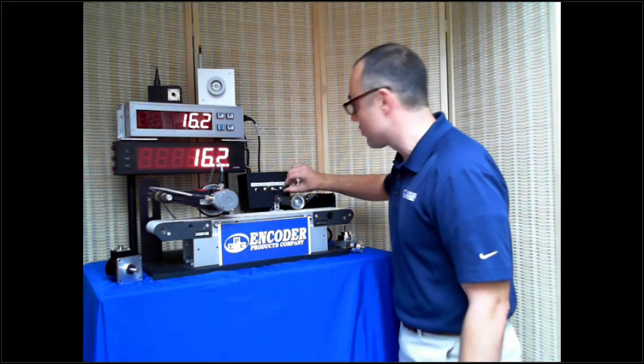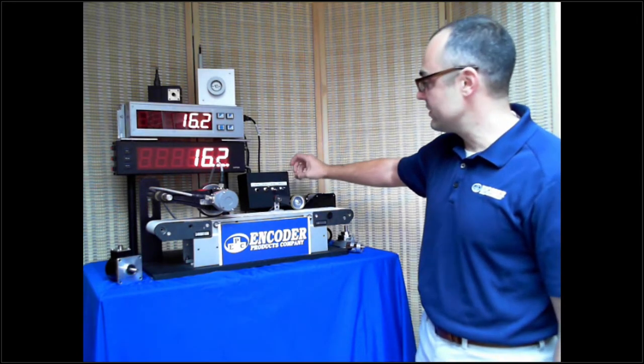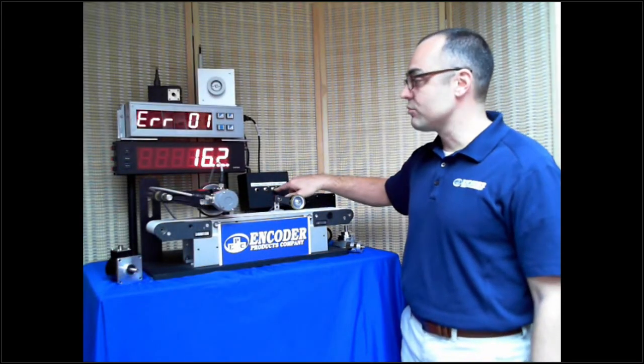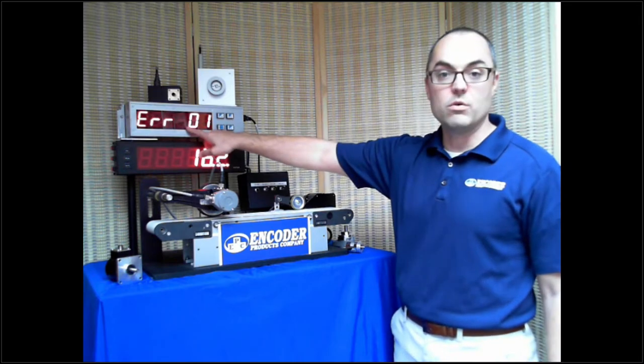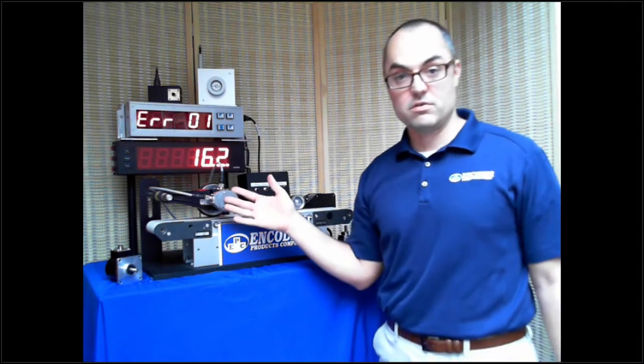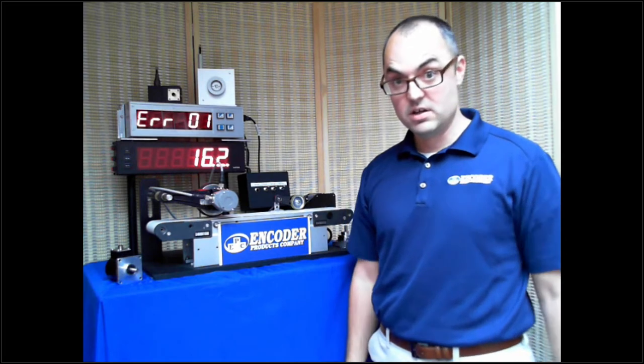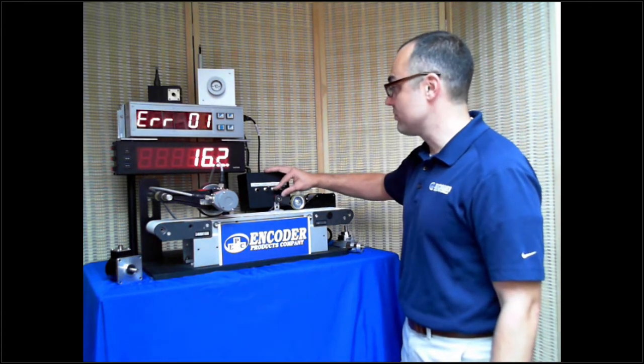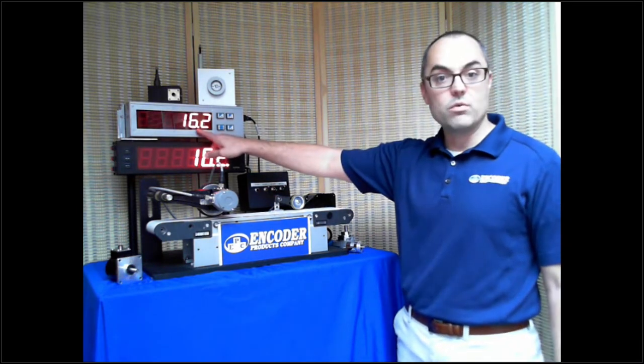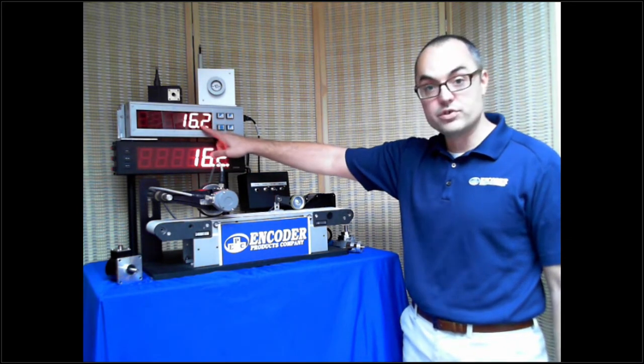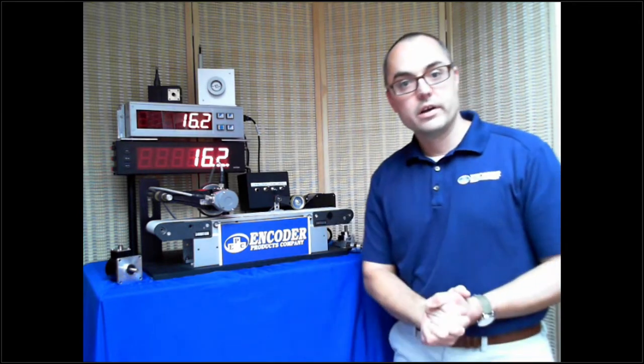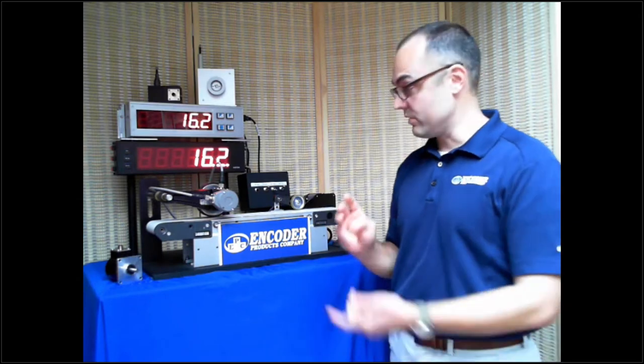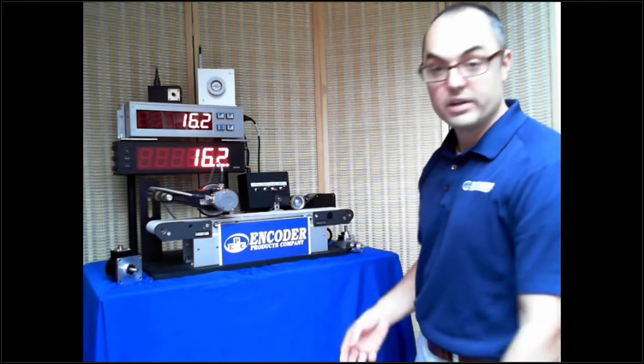If I were to stop this conveyor and turn the absolute encoder power off, so when I flick this switch here, there we go, I click our absolute power switch. You can see I got an error one, which means my absolute encoder is no longer talking. I just cut the VCC circuit right out of there - it's off. When I turn this absolute power back on, it goes right back to where it was. It didn't forget, we didn't go to zero, we went back. Well, that's great, Jared, but that just means you're storing the position.